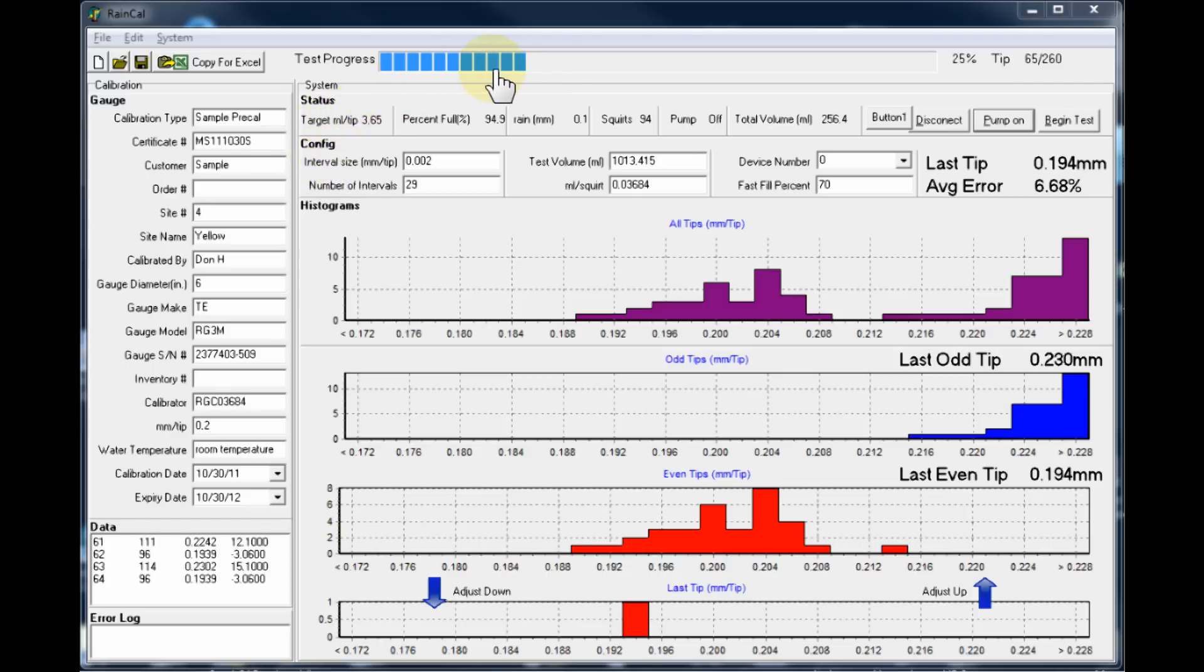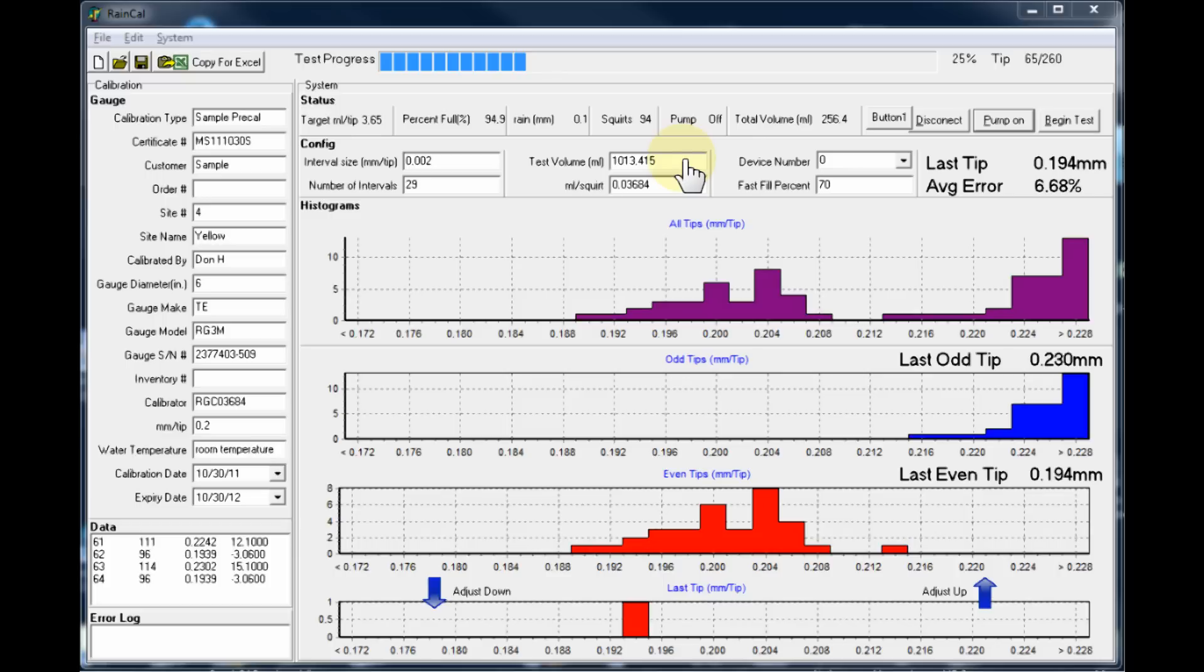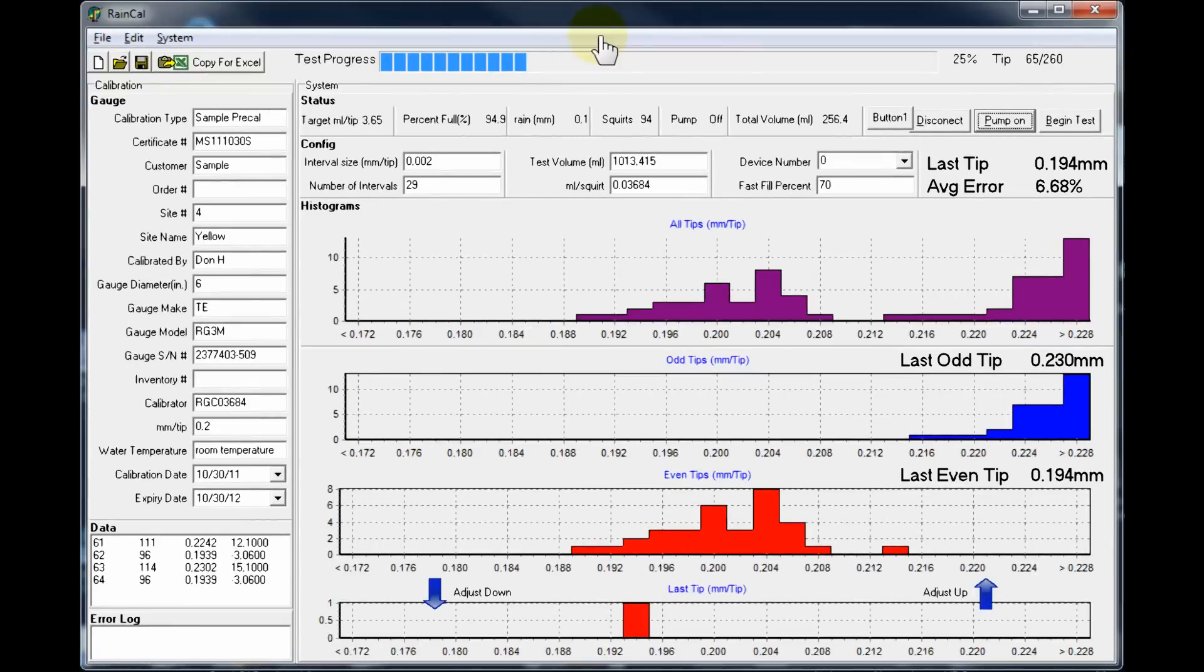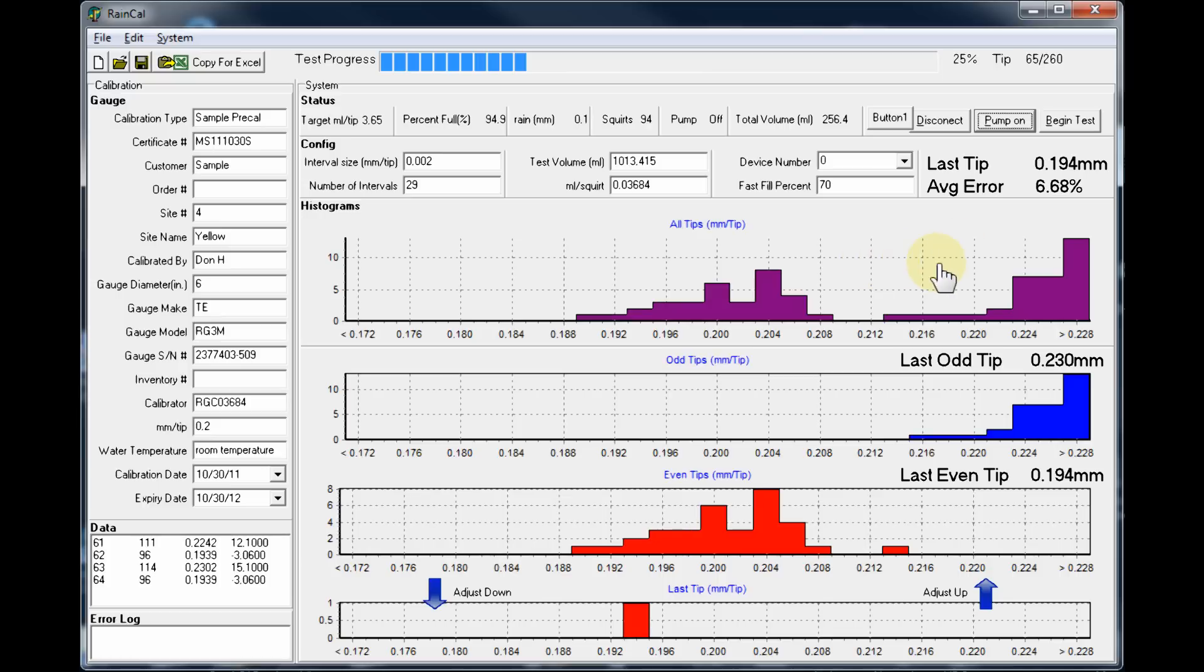Along the top of the screen, we can see the progress bar, and that tells us what portion of the total test volume we have used. In this case, we have used about a quarter of the test volume, so we're about 250 milliliters out of a liter. Now we'll take a look at how the software provides us information on what the rain gauge is actually doing on the calibrator.